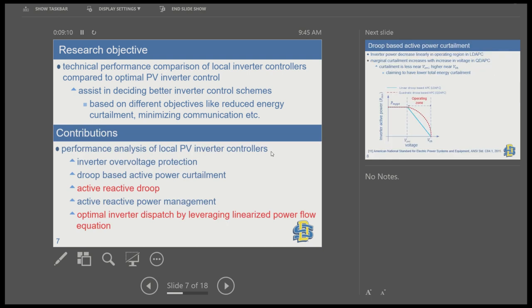The contribution of this work is a framework where any PV inverter control approach can be evaluated to see how far it is from optimal performance. We compare four different local inverter control approaches: overvoltage protection (shut off the inverter), droop-based active power curtailment, active reactive power droop, and active reactive power management.